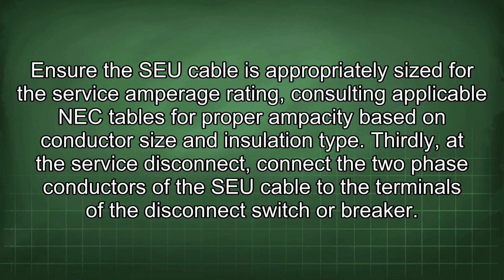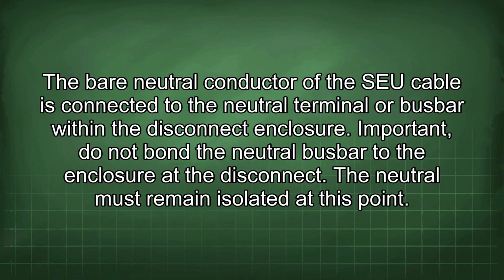Thirdly, at the service disconnect, connect the two phase conductors of the SEU cable to the terminals of the disconnect switch or breaker. The bare neutral conductor of the SEU cable is connected to the neutral terminal or busbar within the disconnect enclosure. Important: do not bond the neutral busbar to the enclosure at the disconnect. The neutral must remain isolated at this point.